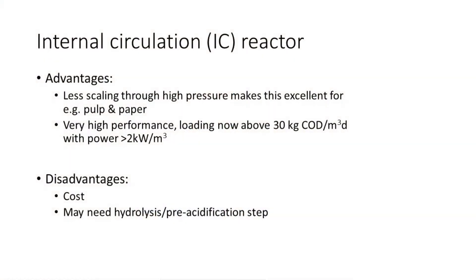The internal circulation reactor is a tall, self-mixed, intensive reactor with specific advantages. Because it's tall — 20 to 30 meters — the high pressure limits scaling: calcium carbonates are kept more in solution. So if you have a pulp and paper wastewater, you have fewer issues with scaling. You get a very high performance: conversions over 30 kilograms of organics per cubic meter per day, which is more than 2 kilowatts of power per cubic meter of reactor. That is a lot.